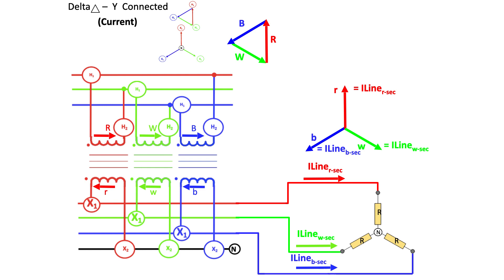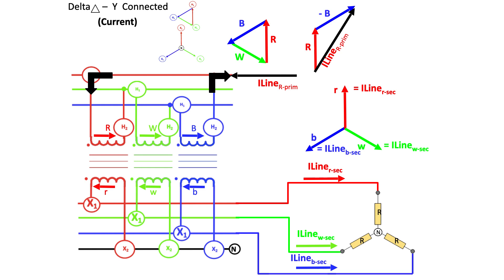Once the load is connected to the secondary, it will draw current from the primary lines. Looking at the red phase line, for example, it will be made up of the current flowing in the red phase transformer winding minus the current flowing in the blue phase transformer. Adding those two vectors or phasors together gives us the total current flowing in the red phase primary line, which forms an isosceles triangle whose contained angles are 120 and two at 30 degrees.